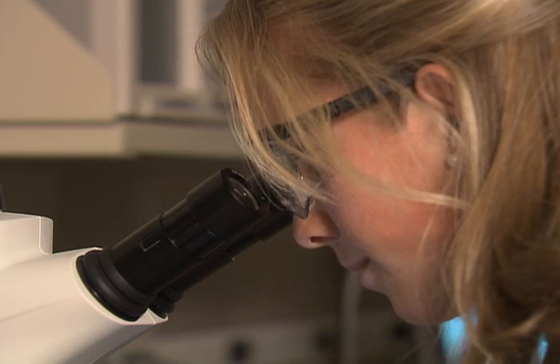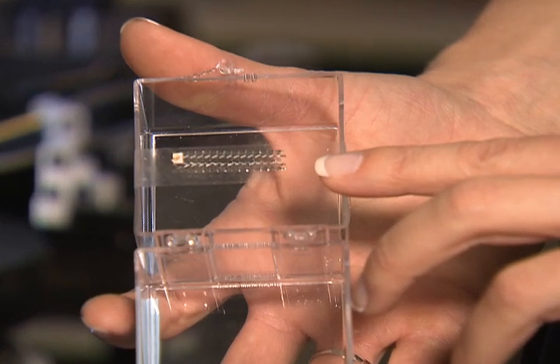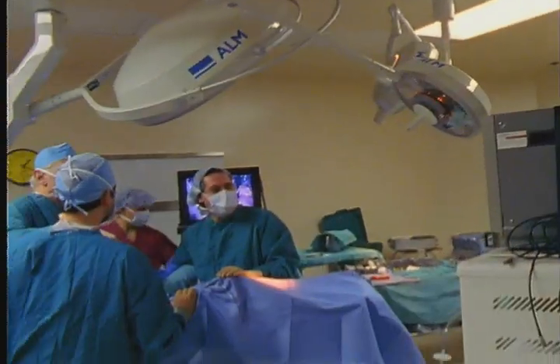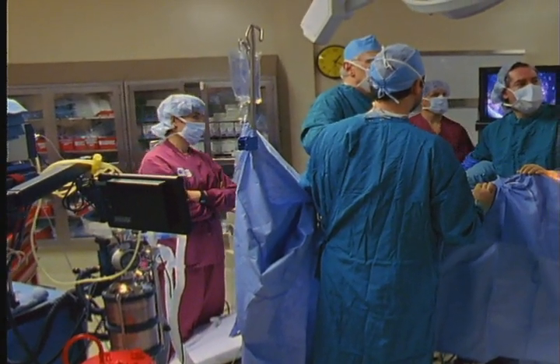Our device consists of a sensor and an application-specific integrated circuit. This device is integrated with either a stent or a nitinol loop, and these two things act as the antenna for the device. We implant the device either with a catheter or some other method in the pulmonary artery, and from there this device can wirelessly transmit the blood pressure data to an external receiver which a clinician could hold outside a person's chest and actually download this continuous pressure data 24 hours a day.